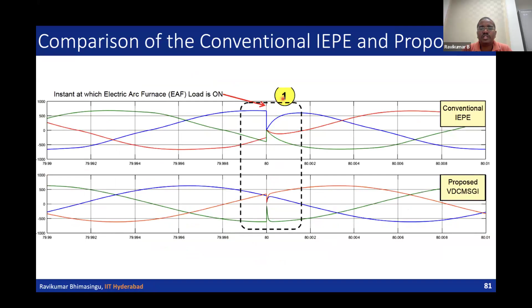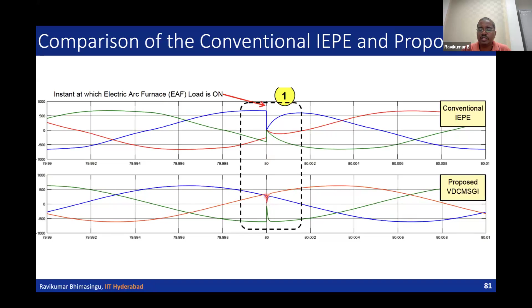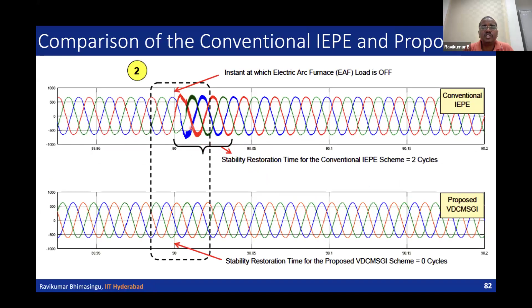This is the case where the electric arc furnace load is turned on. You can see that on the conventional IEPE scheme, all three-phase voltages become zero, but here the dip is not much. The moment the electric arc furnace load is turned off, the restoration time here shows almost no deviation, but for the conventional scheme the restoration time is almost 2 cycles.